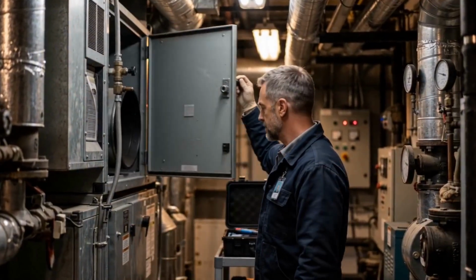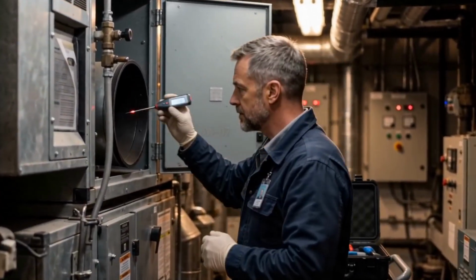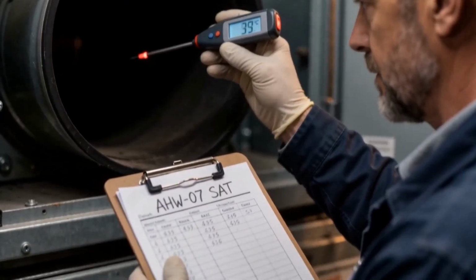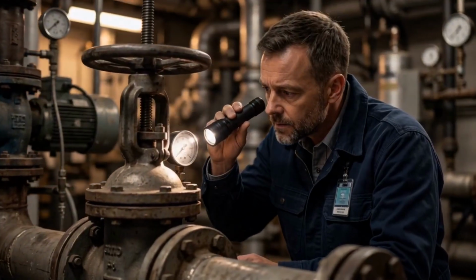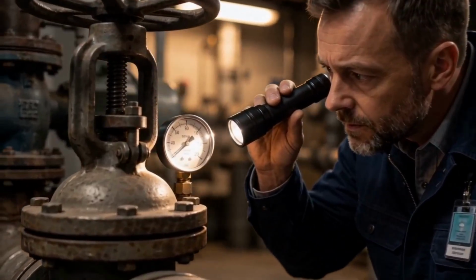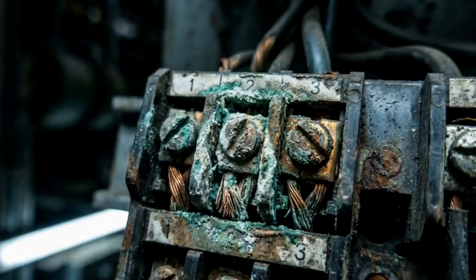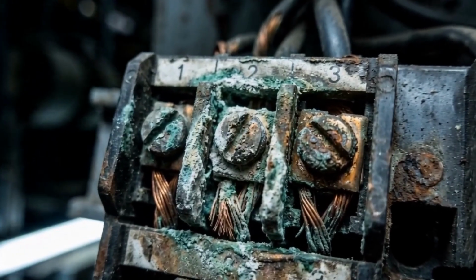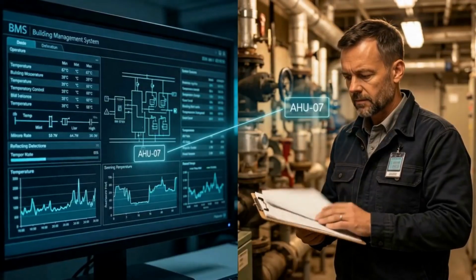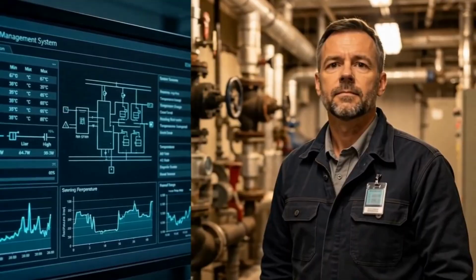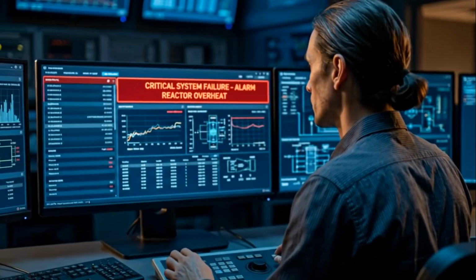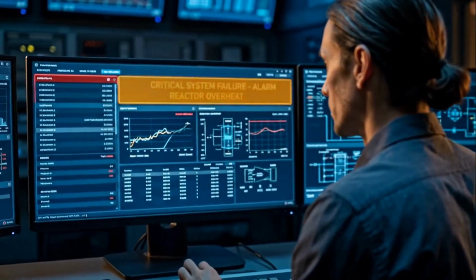If the BMS says supply air is 55 degrees Fahrenheit, a strong operator measures discharge with a calibrated thermometer. If the BMS shows a valve at 80% open, they check the actuator position on the valve body. Sensors drift, actuators fail, wiring corrodes. A system can show stable graphics while the building quietly underperforms. Field verification is how you catch it. The BMS is the most powerful tool an operator has, but it's only as reliable as the person using it. Learn the system, learn the equipment, and trust your hands as much as your screen. That combination is what makes a strong operator.